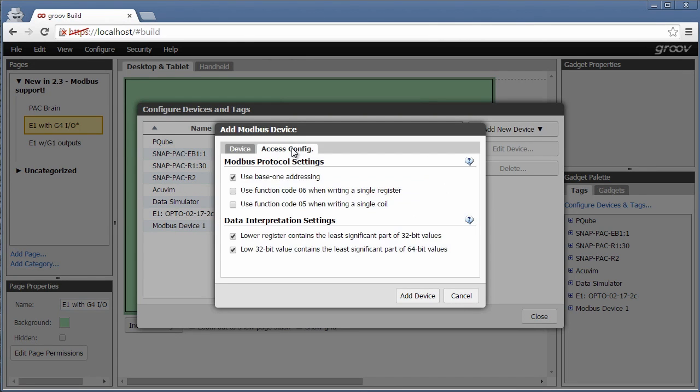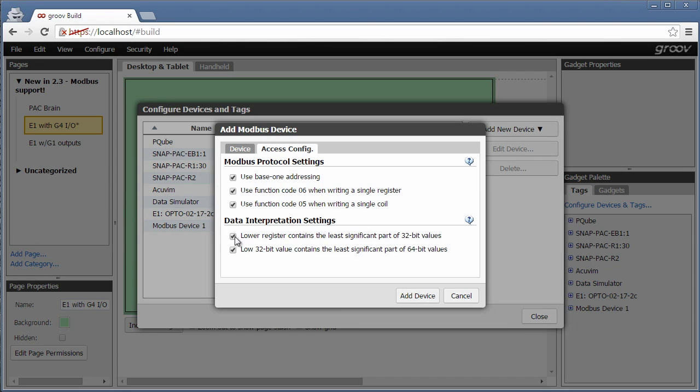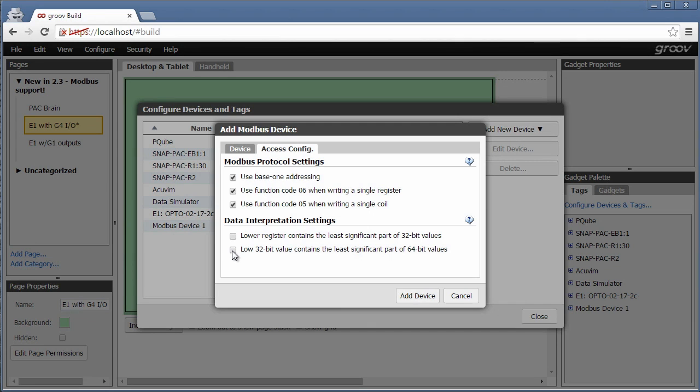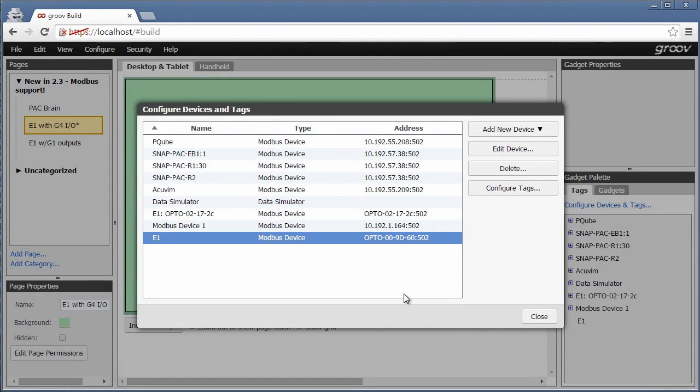The defaults are fine for the slave ID and port. Next, click access config and check these Modbus protocol settings. We have yes, yes, yes, and then no and no. Since the Modbus standard is interpreted by device manufacturers in a variety of non-standard ways, we provide lots of options here so Groove can connect to just about any Modbus TCP device. Click add device.